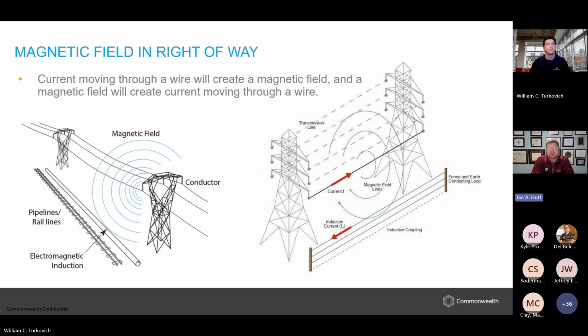On the fence, depending on the fence conductors or composition, we can have different impacts, and you can induce a current or voltage on that fence, which can be pretty dangerous, especially if that fence is not within a protected work zone, for example outside the right of way of the transmission line, where the public may interface with that fence. So that's something we keep an eye on.